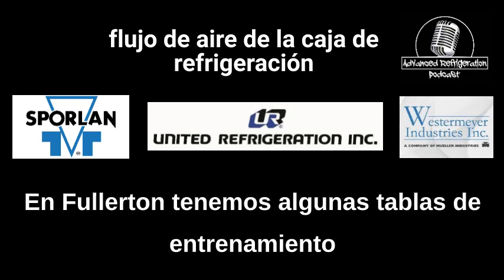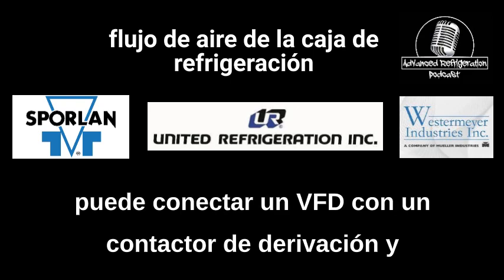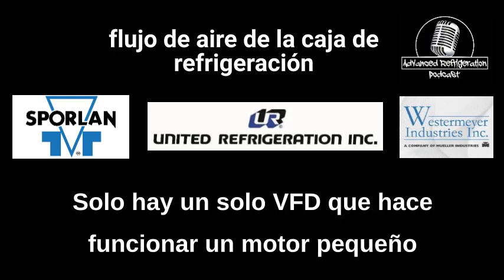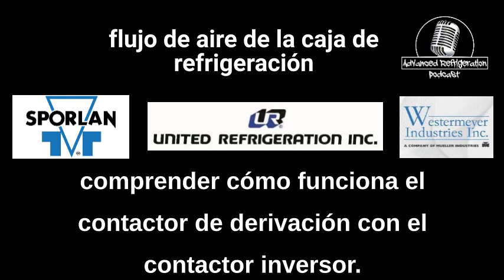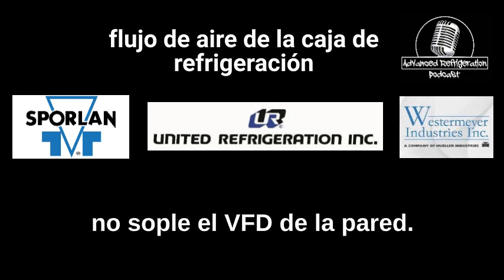We have some training boards that have VFDs on them and stuff. So in part of one of our level classes, they can hook up a VFD with a bypass contactor and all that other stuff that's already mounted on the wall. There's one single VFD that runs one small motor, and they hook it up accordingly to the way it should be, and watch it run just to make sure they understand how the bypass contactor works with the inverter contactor, and making sure that the interlock is there so you can't pull in both contactors and so you don't blow the VFD off the wall.